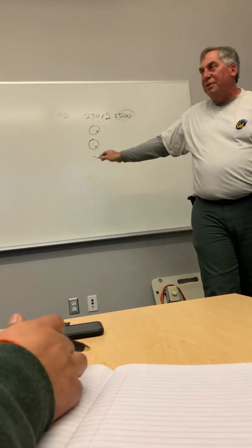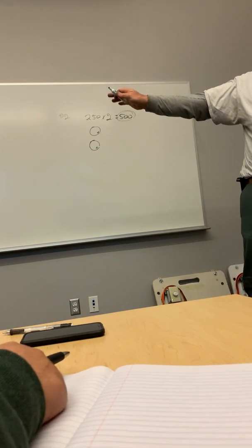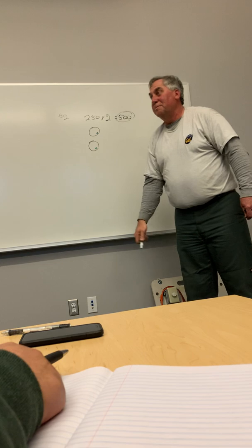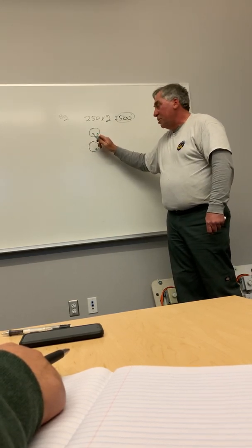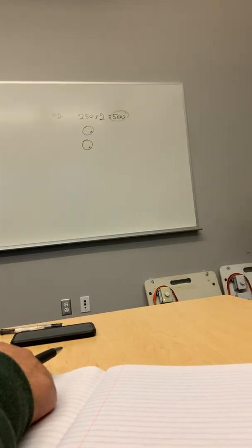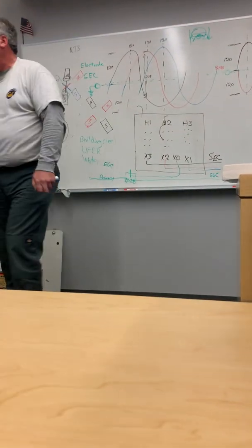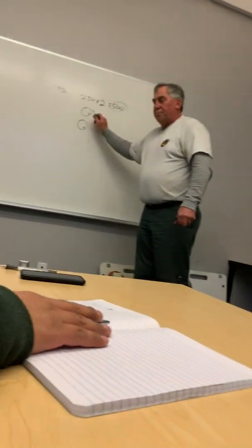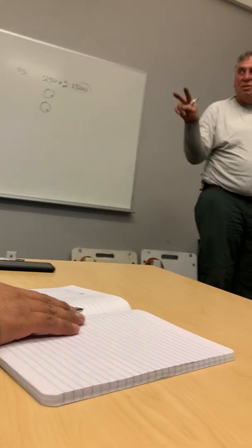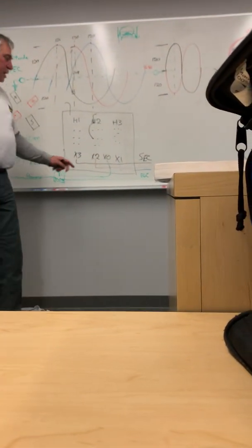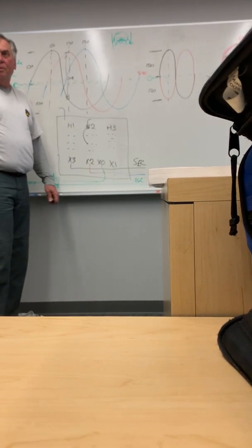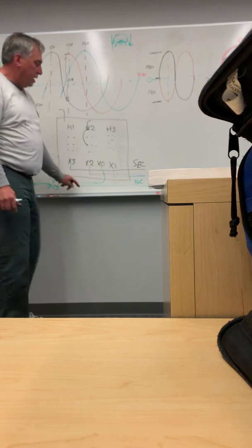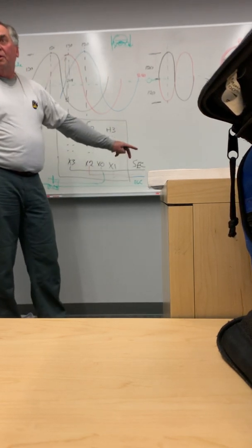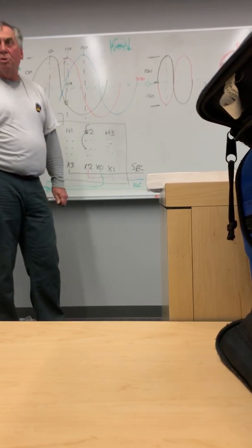I've had guys do this. They get all the way to final, the inspector comes out, they're doing their service, they're getting their green tag, and they changed the number up here because they thought it was in parallel. They didn't give it the full grounding conductor it needs to bleed off that extreme voltage that's going to be induced on this if you have a problem, right? So that's why that number 2 is sized, and this grounding conductor that's coming off of the transformer for the separately derived system. There is no overcurrent protection on this side. The only overcurrent protection is the fusible link of that wire, right? So whatever that wire can carry, we need to make sure we have a grounding conductor big enough to carry that fault current to where it'll trip or do what it needs to do.